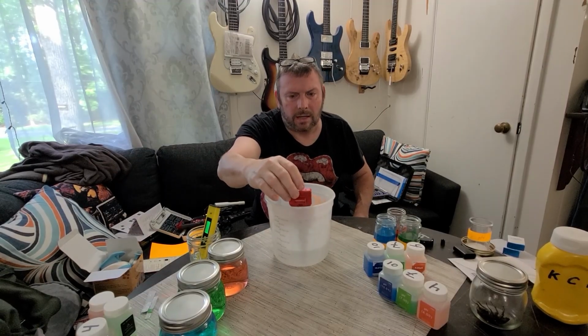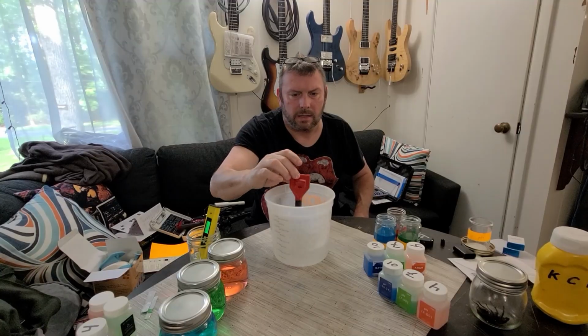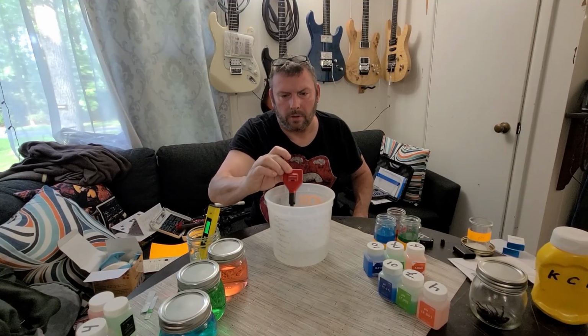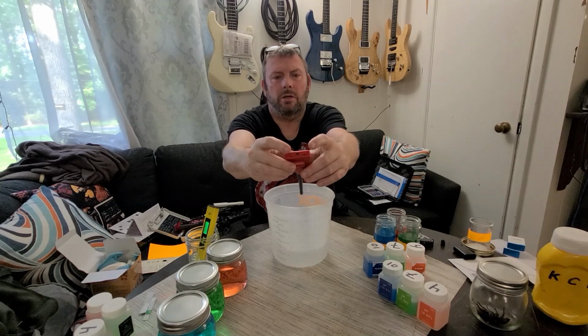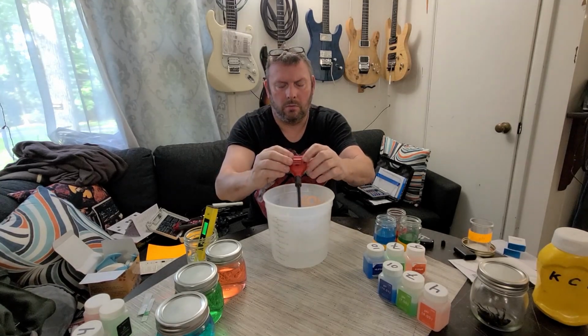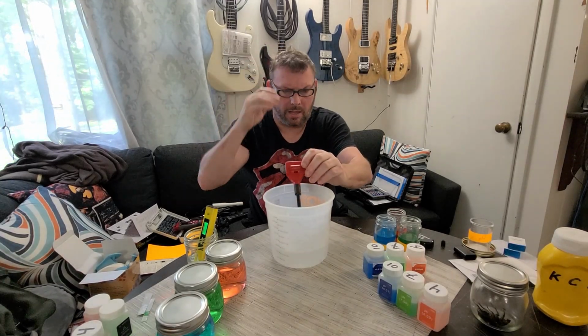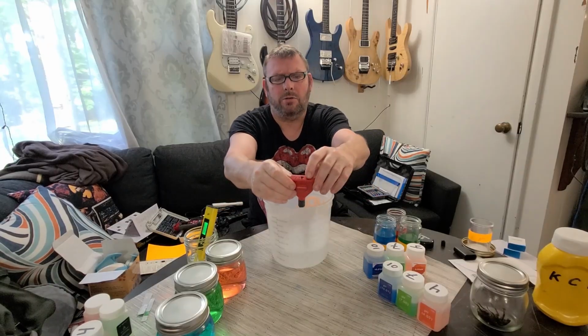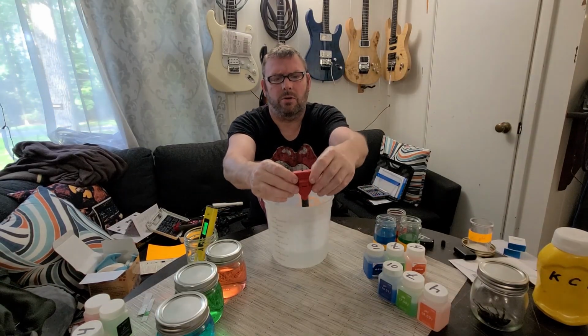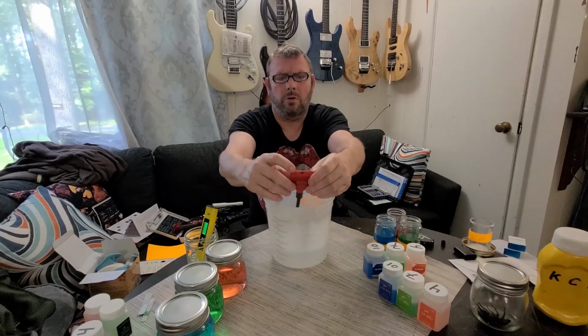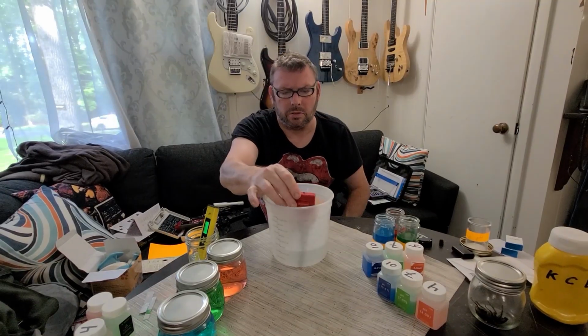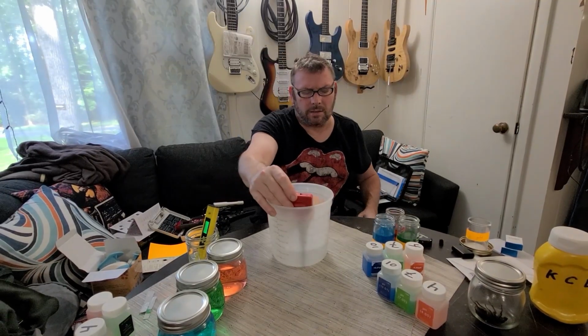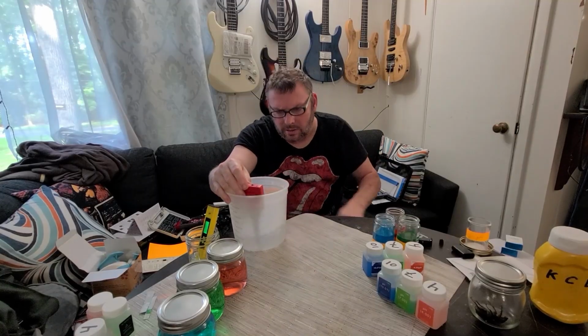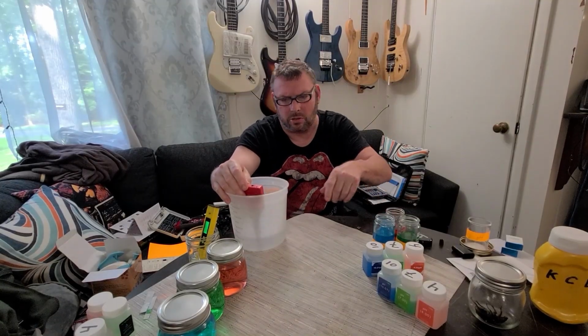Now, how they say to calibrate this is they say take a on-off button. There's 2 calibration screws on this, a high and a low. The one on the left, the blind man glasses, you calibrate your 7 here. There's just a little set screw, and then either your 4 or your 10 gets calibrated with this screw. So it's the same as before. We got it now. This time though, this doesn't want 6.86. This wants a 7 solution.